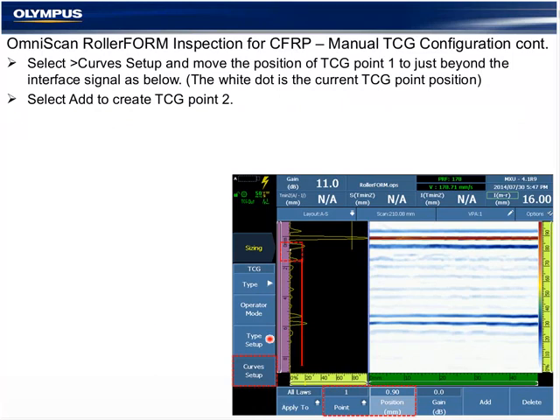After TCG is selected, select Curve Setup, and you will see a default point 1 with no gain at 0 millimeters by default. We're going to move the position, and we can see the TCG point is the white dot right at 0 amplitude on the UT ruler. We're going to increase the position here to move our TCG point slightly off the interface so that no gain is realized prior to the TCG point. Select Add to create TCG point 2. And by the way, this same TCG curve is applied to every A scan. This is A scan first. This is A scan last on the S scan. It's applied evenly to all of them.